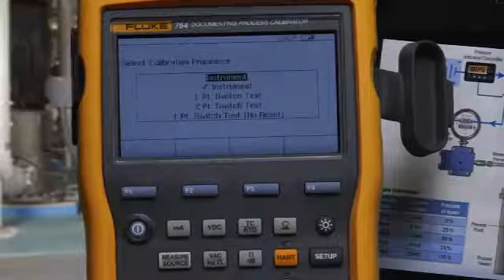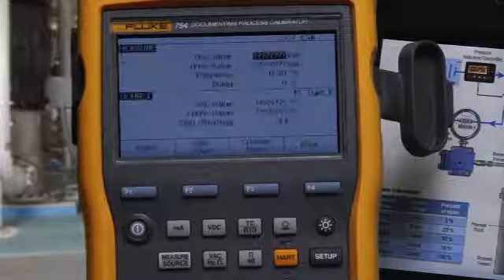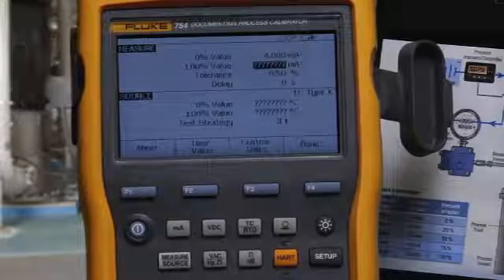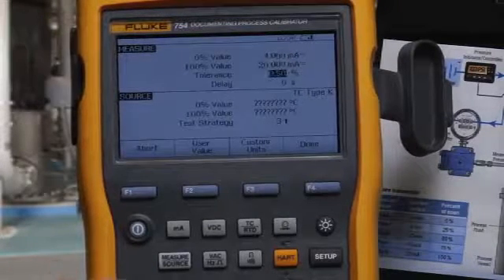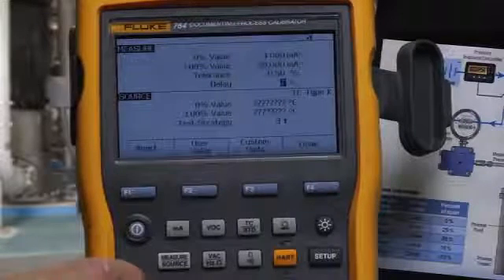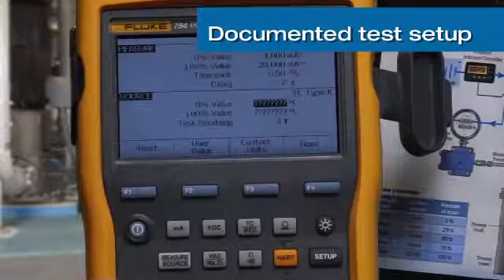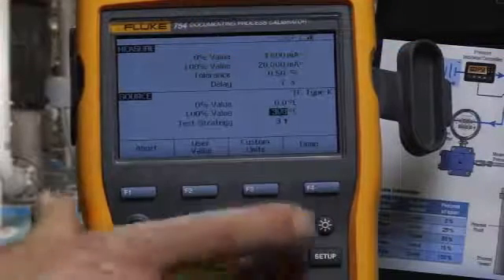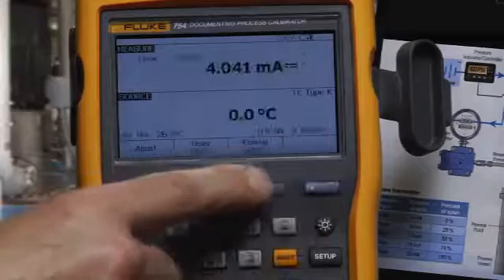Configure what we're going to measure, 4 to 20 milliamps. 0.5 percent. Set settling delay and source 0 to 300 degrees C and a three-point test.